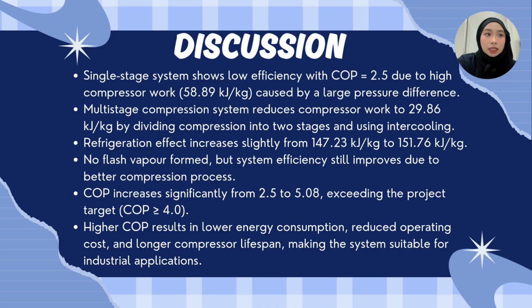As a result, the COP reaches 5.08, exceeding the project target of 4.0. This higher COP lowers energy consumption, reducing operating costs, and extends the compressor's lifespan, making the system well suited for industrial application.